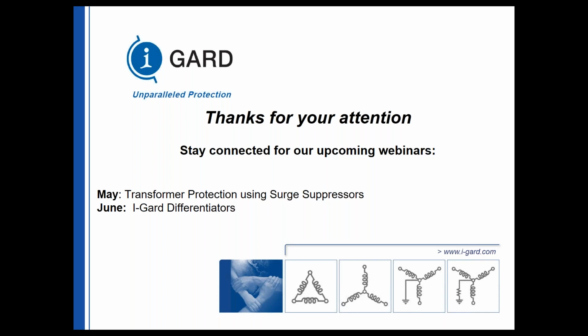Okay, I think what you're asking me is, does the capacitor apply a voltage onto the conductors while you're working on it? It does not. The only time the absence of voltage tester uses the capacitor is to perform a continuity test and to verify that the meter is working, to verify that the functionality of the i-AVT has been done correctly. No voltage is present on the bus, and this only occurs after you've pressed the test button and after you get the 3 green LEDs. The capacitive voltage does not appear on the bus. It doesn't go on there, so you don't have to worry about it. So opening the panel door does not put you at a higher rate of risk because of the capacitor.